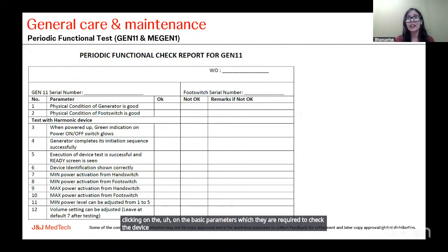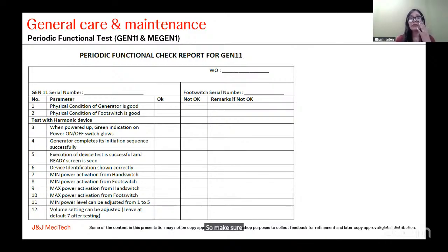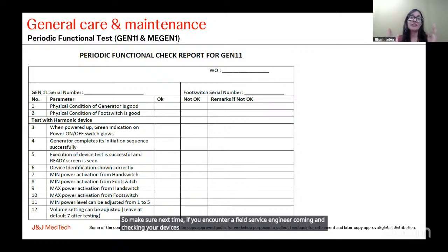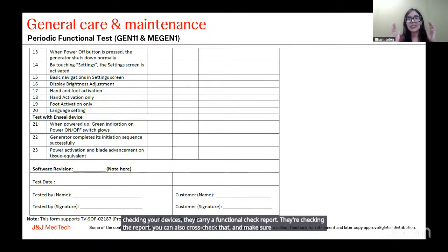Are they checking the external components of the device? Are they opening the device? Are they checking the internal components of the device? Are they checking the output of the device or not? So make sure next time if you encounter a field service engineer coming and checking your devices, they carry a functional check report. They're checking the report. You can also cross check that and make sure they're going back with a proper report in their hand.